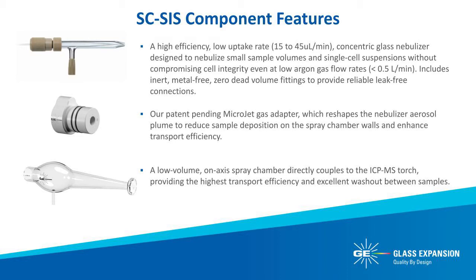Unlike typical concentric nebulizers, the Micromist HE is designed to reach optimum back pressure at much lower gas flows — for example, around 0.3 to 0.35 liters per minute argon gas flow. The optimum liquid flow rate has been found to be in the range of 20 to 40 microliters per minute, most commonly delivered by a syringe pump, as the Micromist HE does not self-aspirate. All gas and liquid connections are made using Glass Expansion's metal-free zero dead volume fittings to provide reliable leak-free connections.